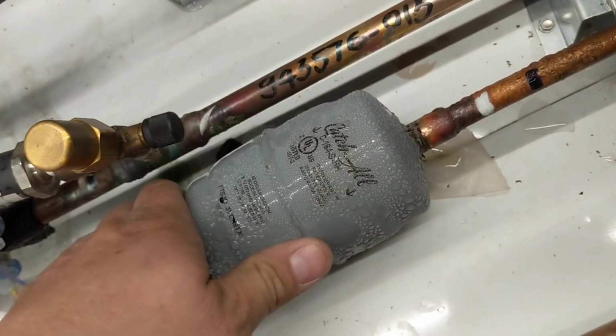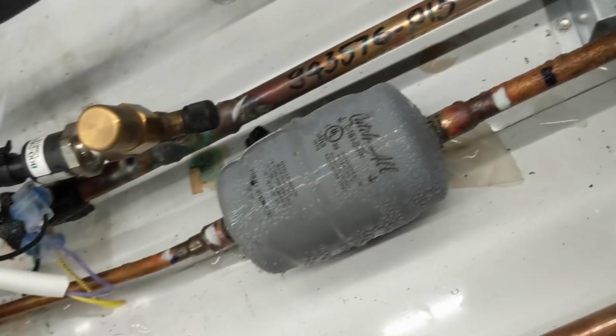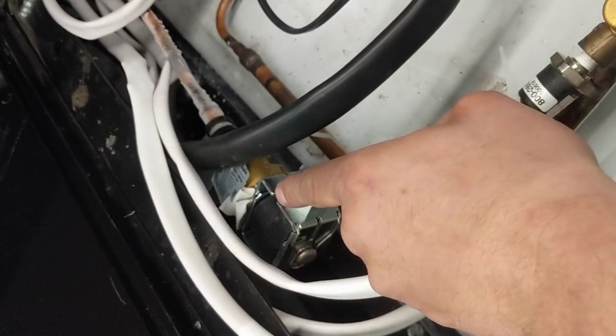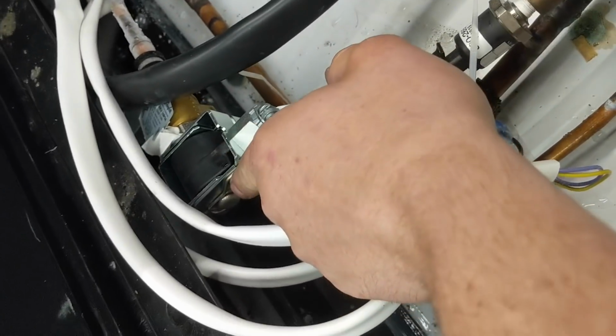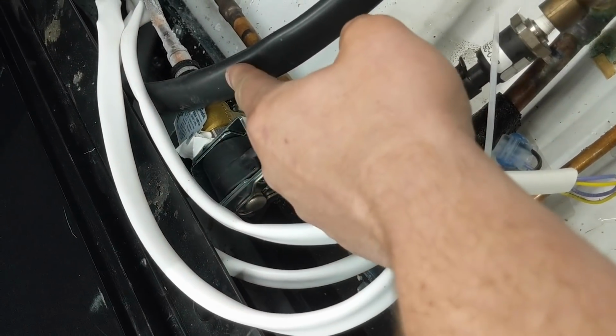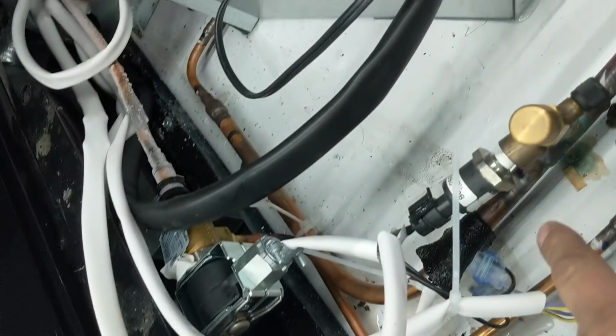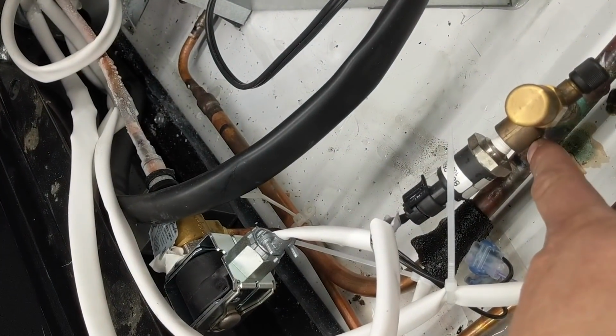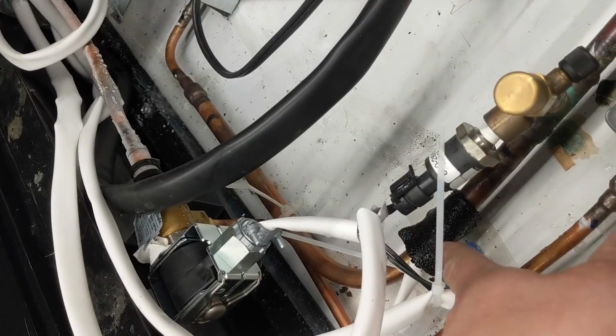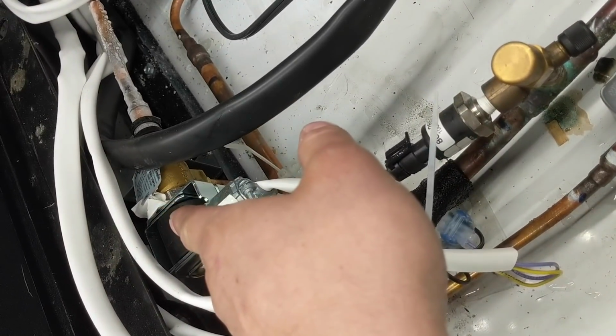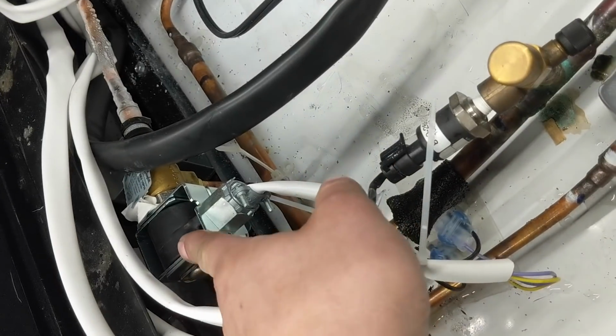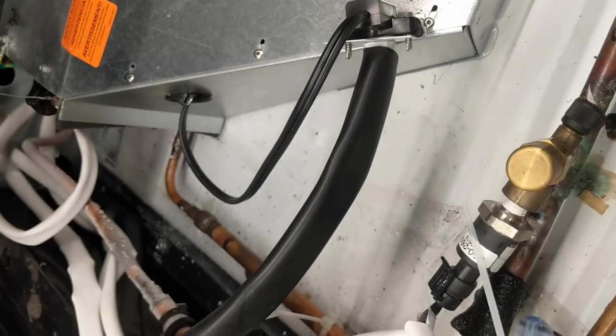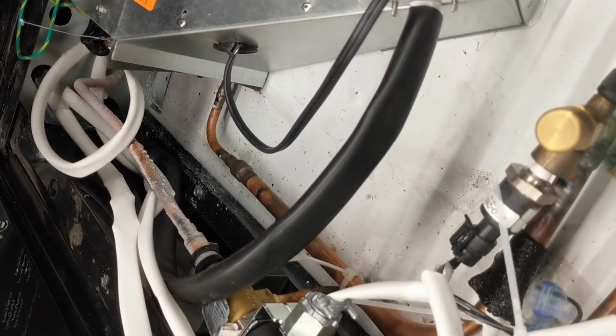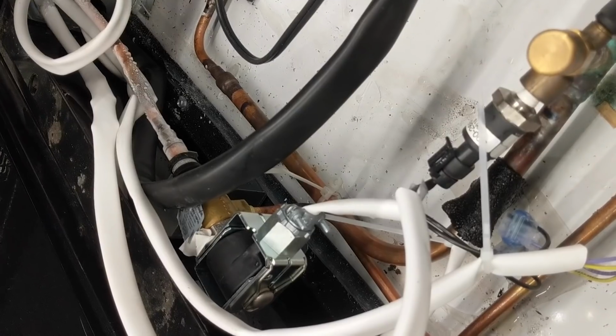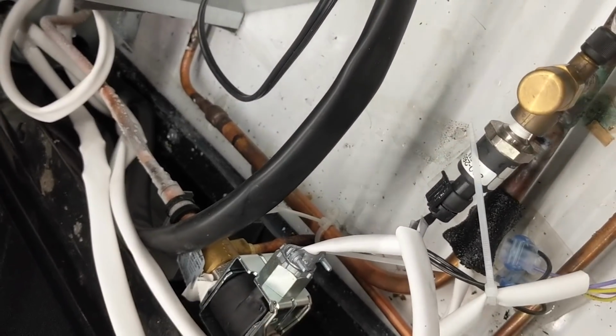We have a liquid line dryer in here. We have a pulse valve. This valve is just pulsing a solenoid on and off, on and off, on and off to maintain superheat that is calculated from the controller from the suction pressure or the temperature and the temperature sensor. It's pulsing the superheat that way. And it's pulsing the valve open, allowing liquid to come in and feed the coil. So that's how it's doing it. It's superheat control and defrost. So when it shuts off, it just stops all flow.